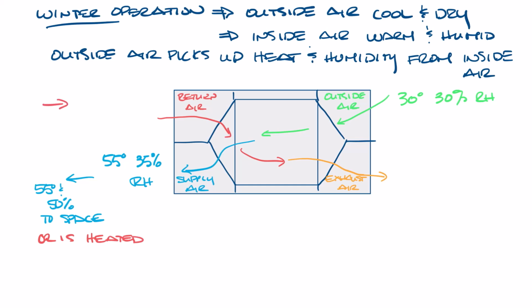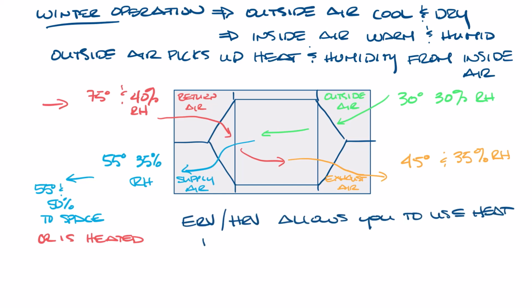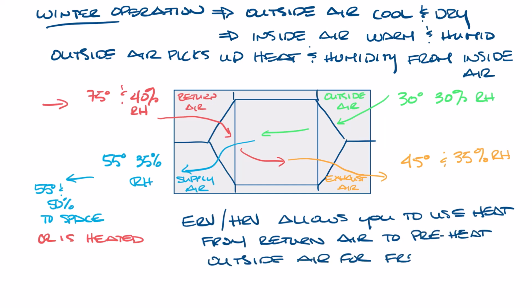And then when the return air comes back, it's 75 degrees and 40% humidity, let's say. And then after it passes through the wheel or the plates again, it's 45 degrees and 35% humidity as it's exhausted out of the building. The ERV or HRV allows you to use heat from the return air to preheat the cold outside air for free in the winter. Now let me move this over one more time.